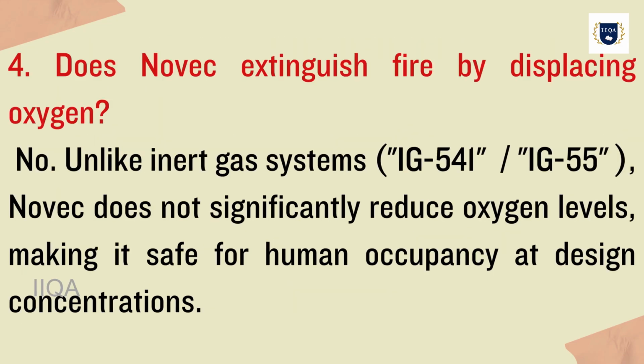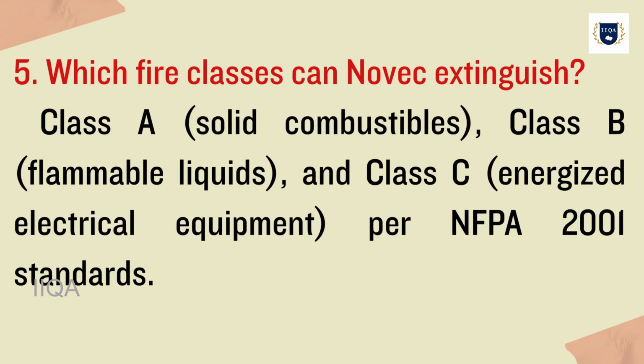4. Does Novec extinguish fire by displacing oxygen? No. Unlike inert gas systems, IG541 and IG55, Novec does not significantly reduce oxygen levels, making it safe for human occupancy at design concentrations.